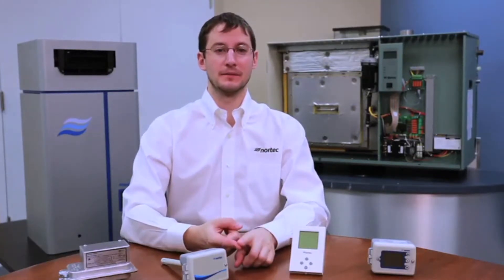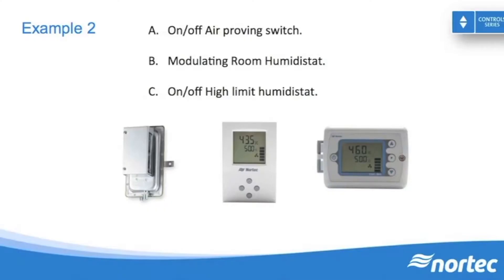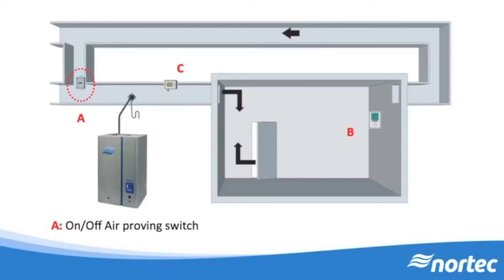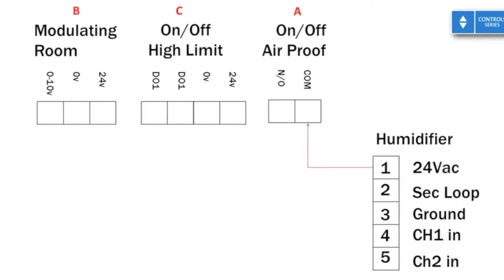Next, let's look at the following three devices: an on-off air proving switch, an on-off high limit, and a modulating humidistat. The on-off air proving switch starts from 24 volts AC on the humidifier's low voltage terminal strip, pin 1. 24 volts leaves the humidifier on pin 1, reaches the common pin of the air proving switch, and when there is airflow, the device closes the connection across the common and the normally open contact, which is then wired to the next on-off device in the loop — the high limit.